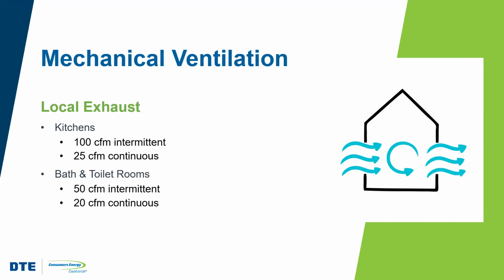Now, in the past, many homes were ventilated manually, mostly by opening windows, but also the opening and closing of doors. Some older homes in Michigan, like mine, have manually operated kitchen exhaust fans. But today, for IAQ purposes, well-designed homes require greater ventilation. And this can either be for the entire house or it can be local to specific rooms where pollutants are likely to be generated. The exhaust air flow rate depends on whether the exhaust is continuous 24/7 or if it's intermittent and only used when needed.